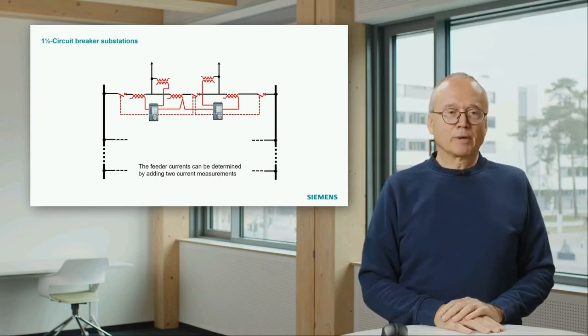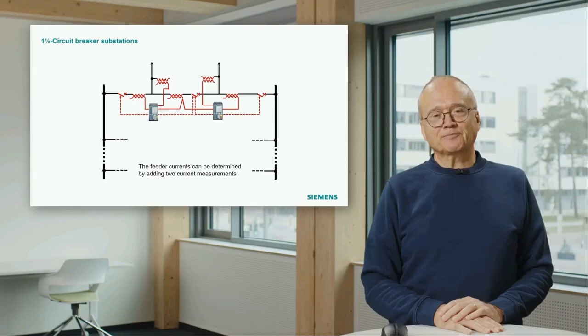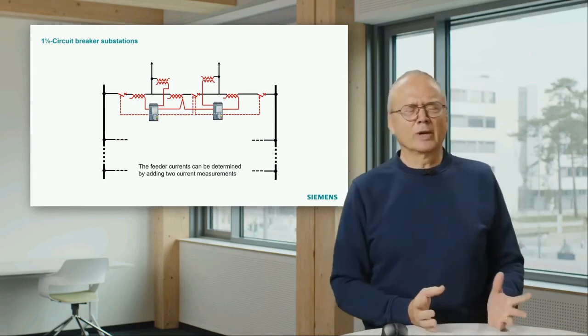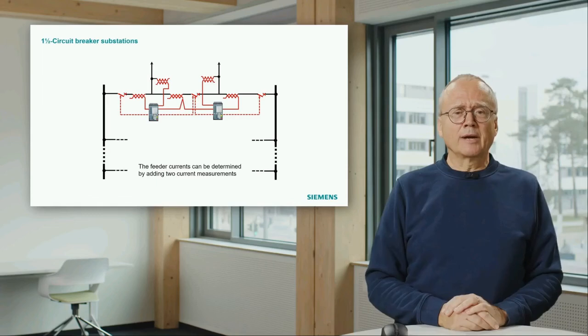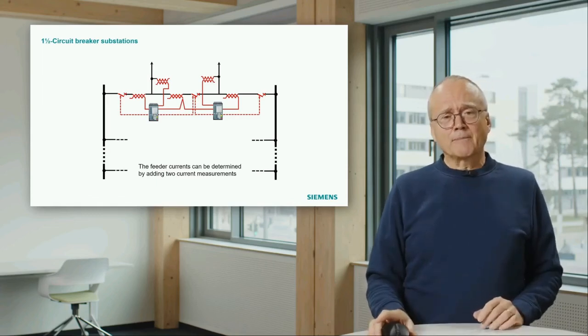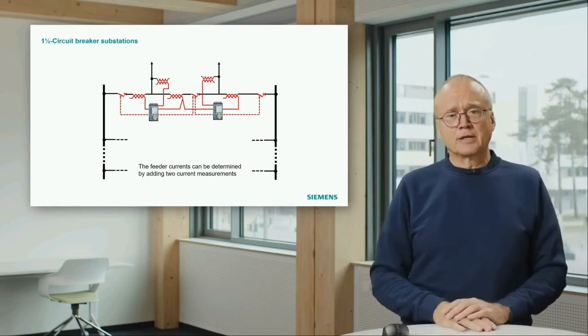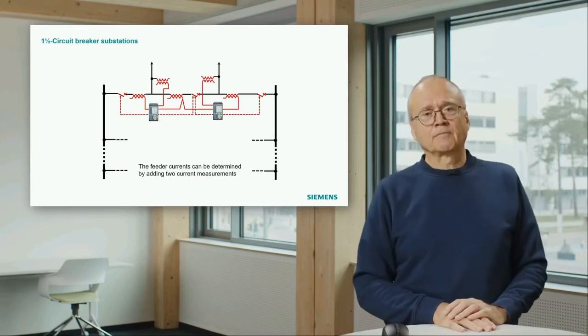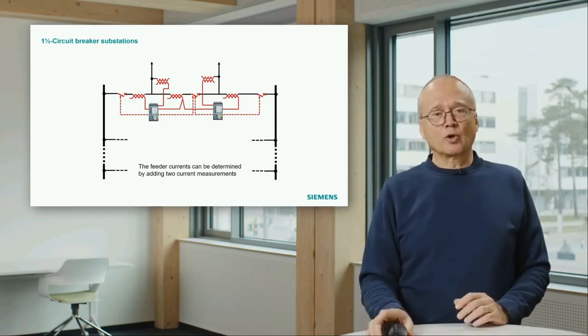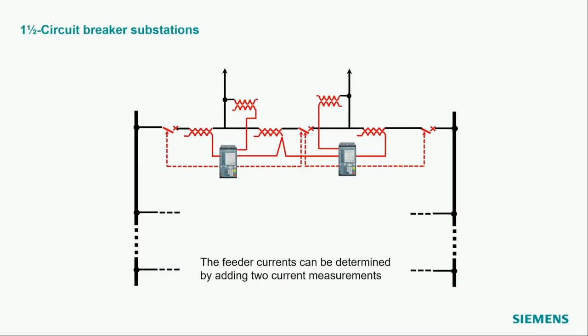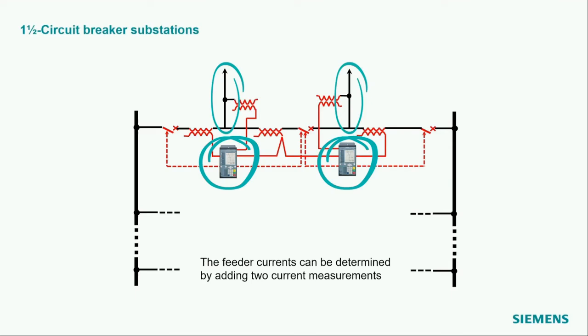That is a so-called breaker and a half substation. It sounds a bit strange. Where do we have half a circuit breaker somewhere? What is the structure there? On both sides you see a bus bar, and to the top we have two outgoing feeders. And in this arrangement we again have one protection relay per feeder. The left protection relay for the left-hand feeder, the right protection relay for the right-hand feeder.